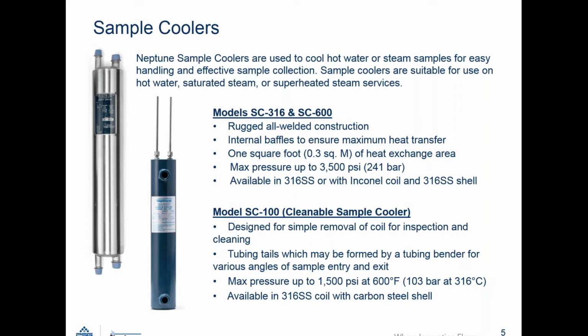That's a maximum pressure of 3,500 psi, and they're available in 316 or Inconel with 316 shell. The SC100, which is this blue one here, is a cleanable design. It has a retainer ring on the top where you can easily remove and pull out this tubing, which the coils that are on the inside where your sample goes through can be pulled out and cleaned.